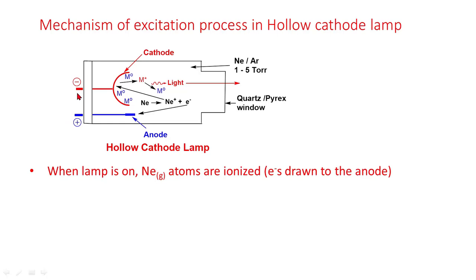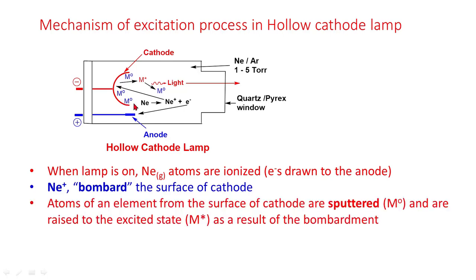Mechanism of excitation process in hollow cathode lamp: When lamp is on, neon atoms are ionized, giving rise to Ne+ and electrons. Electrons are drawn to the anode. Neon cations (Ne+) bombard the surface of the cathode, physically displacing the metal atoms from the surface of the cathode. This process is termed as sputtering.